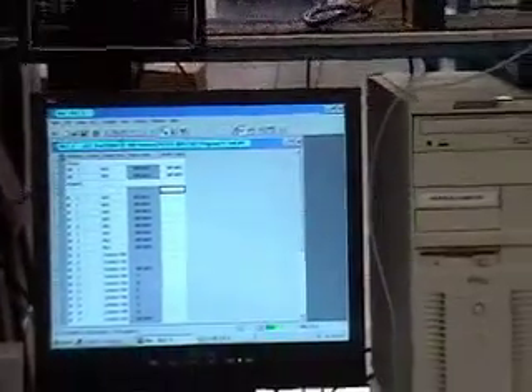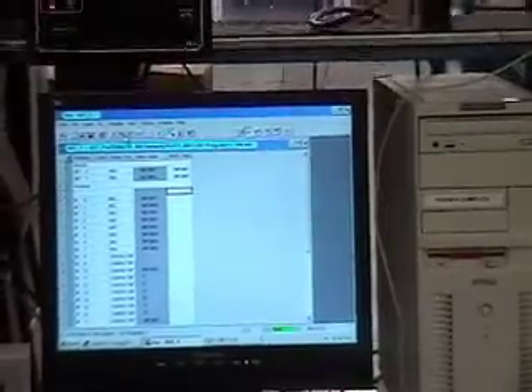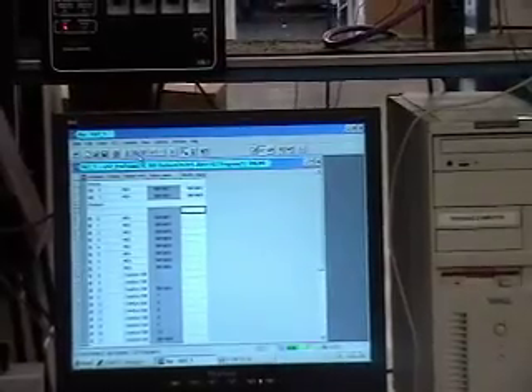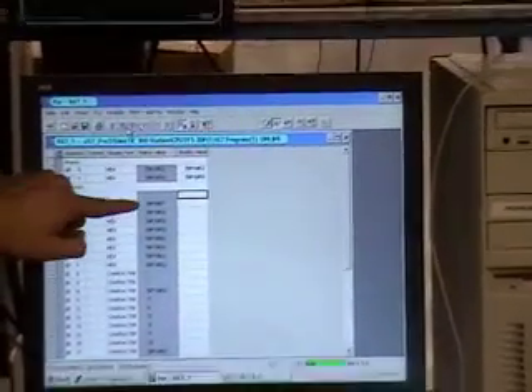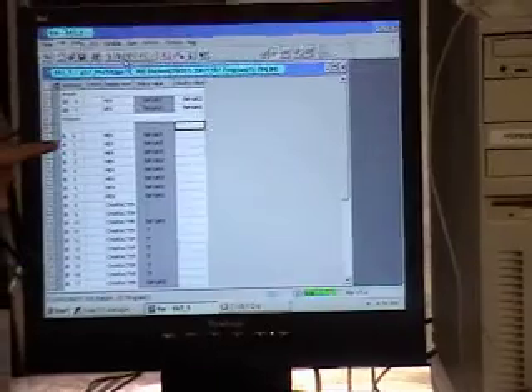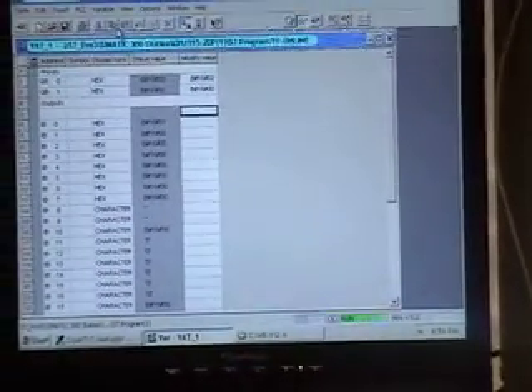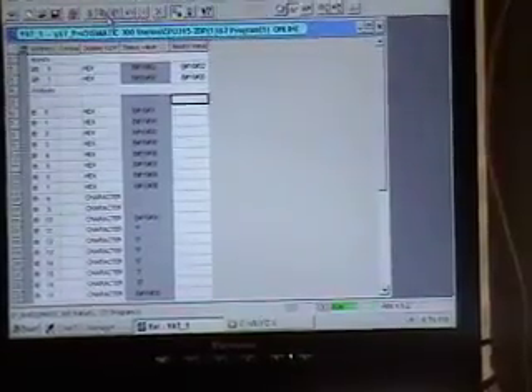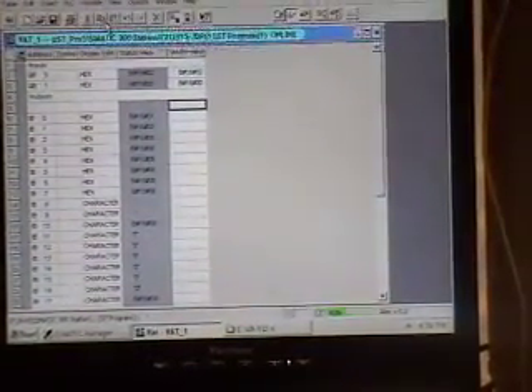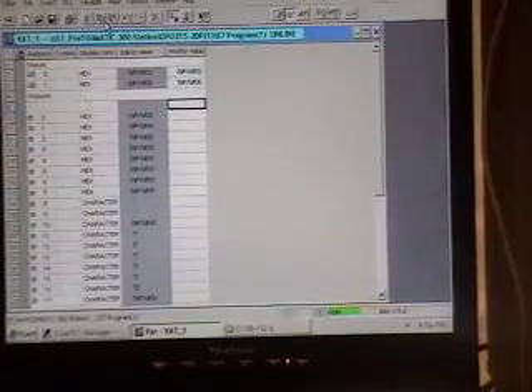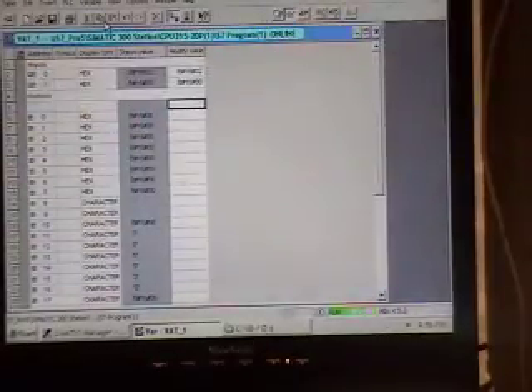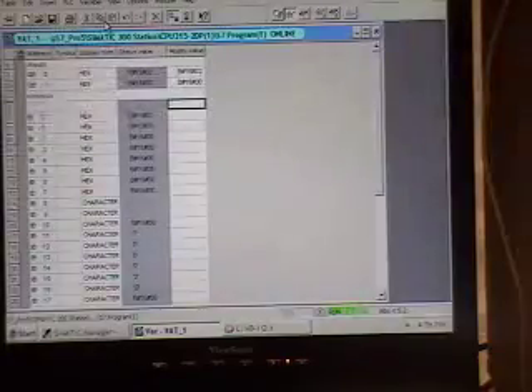Now, of course, with the Profibus, you can get more data than just the manual computer override. That is handy when you don't have a step 7 Profibus network, but you don't get the other troubleshooting data you get from a step 7 Profibus network. You get a concentration here. If you look at the first 4 bytes, the first 4 positions of the output, 0, 1, 2, 3, I'm going to change the cell simulator. And as the oxygen concentration changes, you will see these numbers updating over here. They are hexadecimal or binary numbers, but they basically are the concentration of the analyzer.